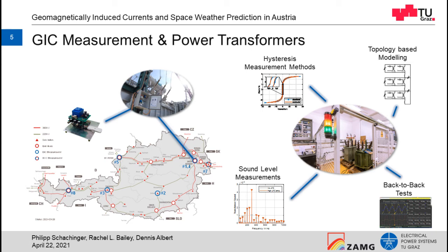We have developed also a hysteresis measurement setup to capture the hysteresis characteristic, and we have tested that approach in the lab, and currently preparations are ongoing to test this approach in the field at large power transformers. Additionally, we perform power transformer sound level measurements with and without superimposed DC to estimate the DC level in the power transformer and to predict the transformer sound level.